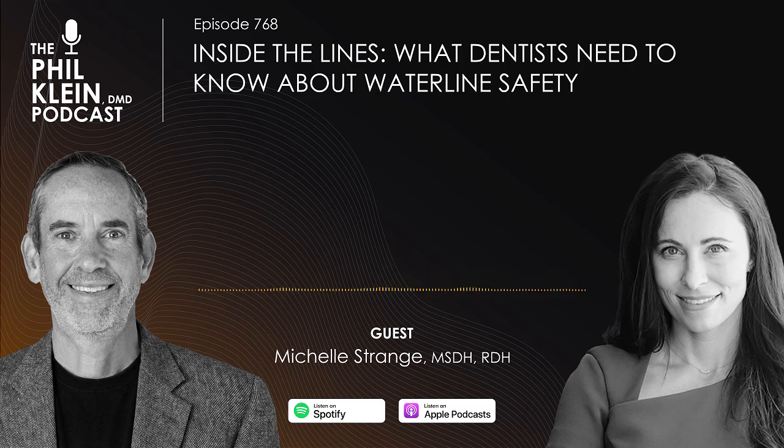That's a great question. So, let's say, for example, I am using my Sterisil straw cartridge system. I put my little Citrisil orange tablet in there. It fizzles once it's done dissolving. I suck that through the lines, and I'm looking for the orange on the other side. So I'm going to pull it through any line that can get water. Again, going back to that slow speed, even though it's turned off, if it can get water, I'm pulling it through.